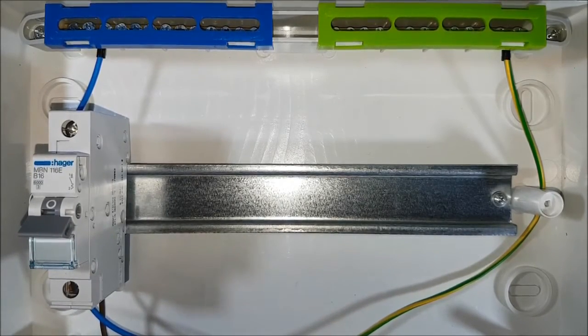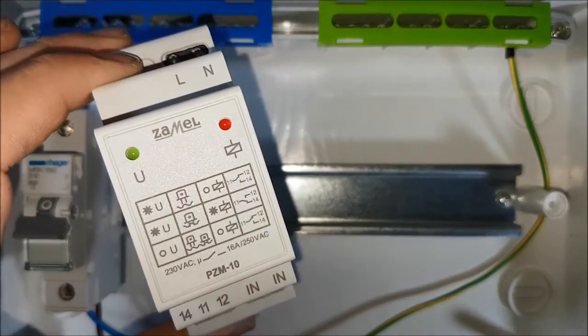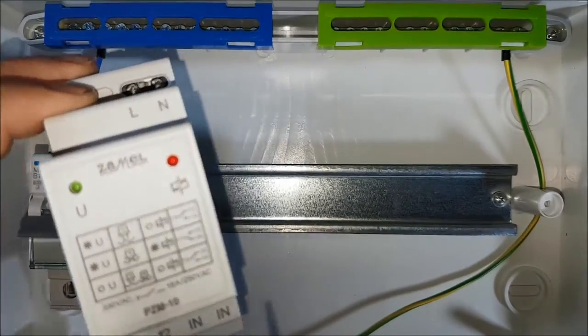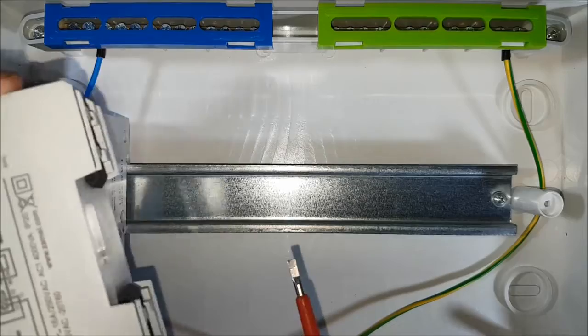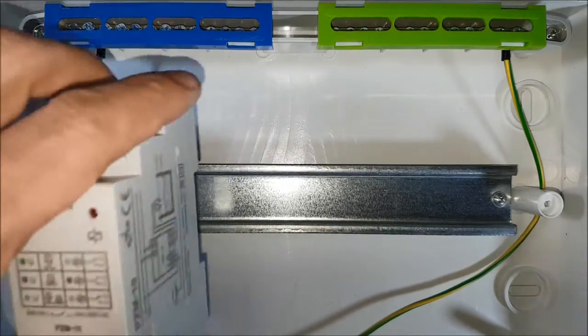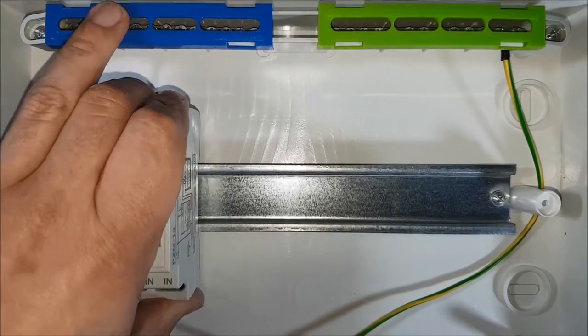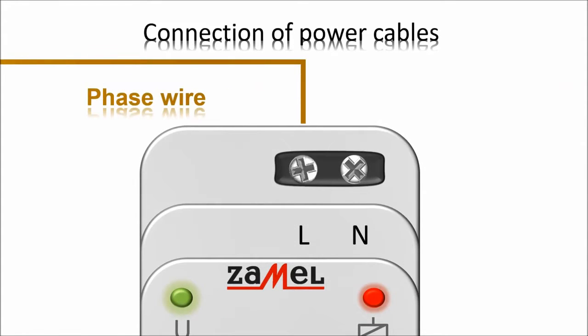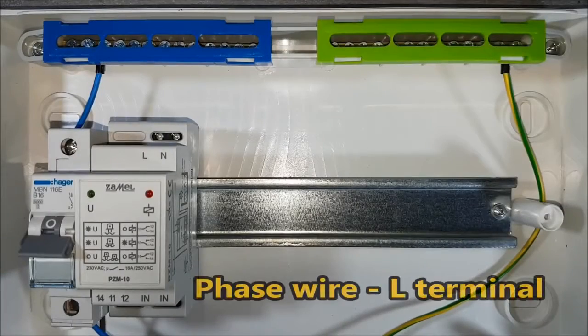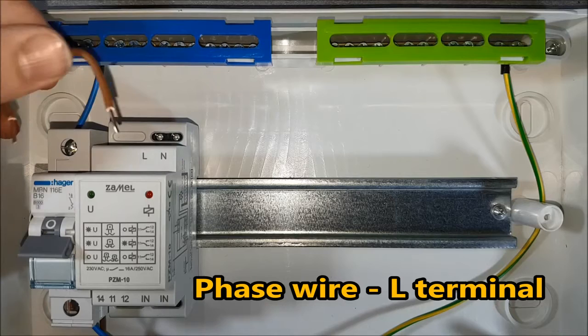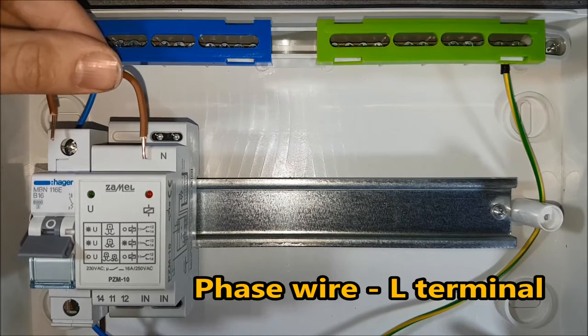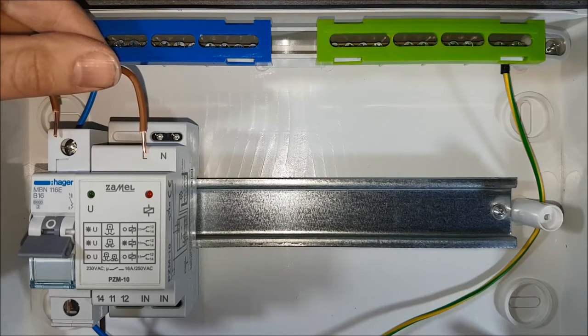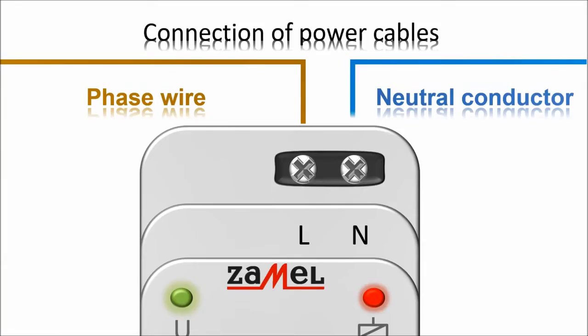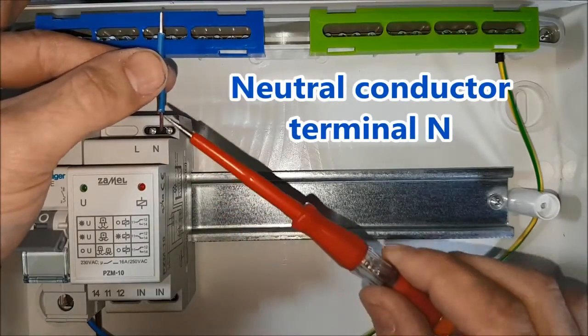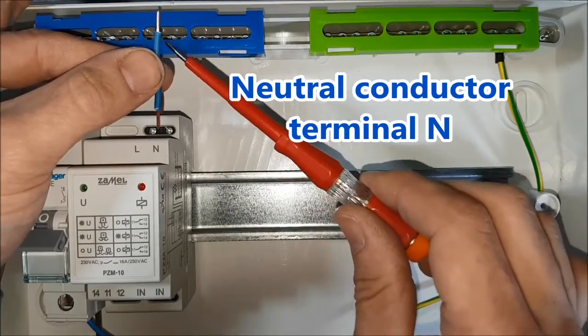Check the disconnection status of the installation. Put the PZM-10 device on the TH35 rail. The spring clips will be helpful. Provide the supply voltage to the relay. Put the phase wire to the L terminal. The neutral conductor goes to the N terminal.